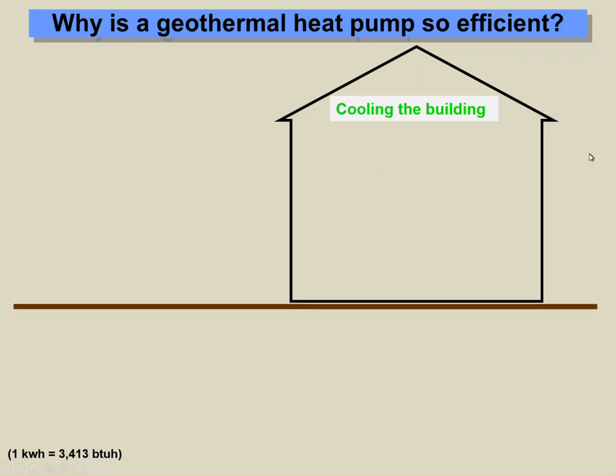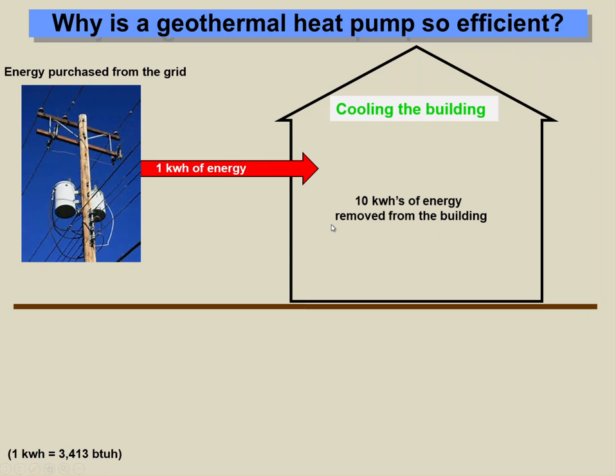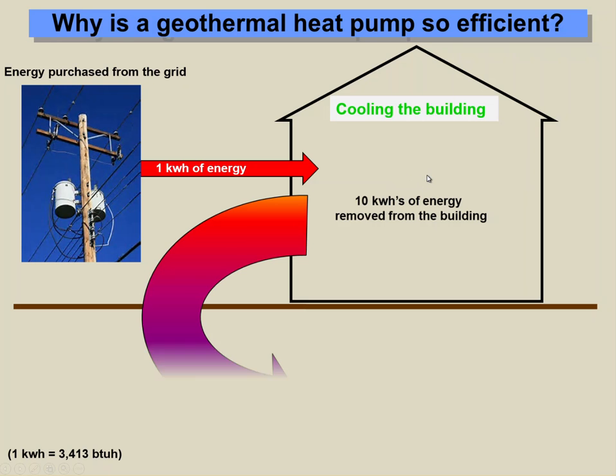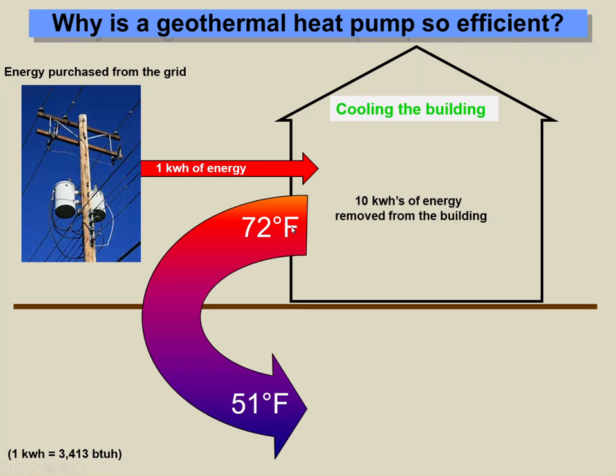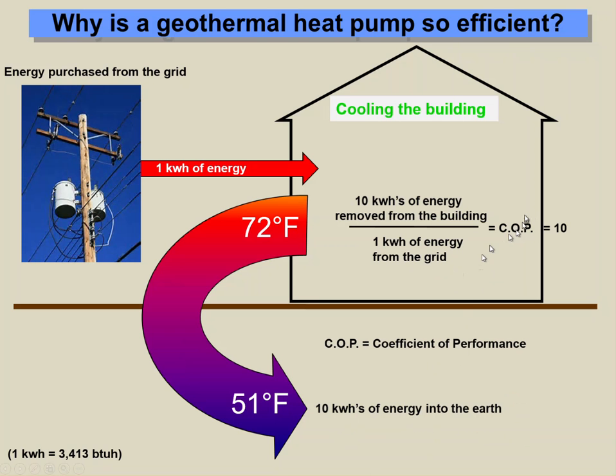When you're cooling the building, you need to reject 10 kilowatt hours of energy into the groundwater. So you buy 1 kilowatt hour of energy to run the geothermal heat pumps, and they reject 72 degree Fahrenheit groundwater into the Nittany Dolomite aquifer, where it returns to 51 degrees Fahrenheit. So 10 kilowatt hours of energy into the earth by paying for one gives a coefficient of performance or efficiency of 10.